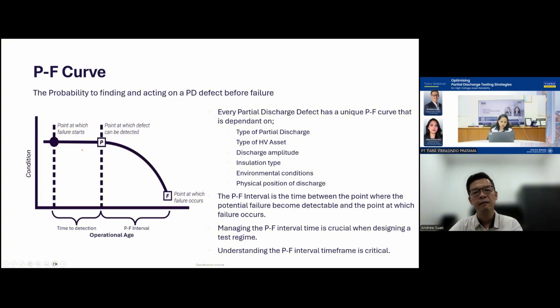Okay, and then number 3, the discharge amplitude. In EA Technology, we have a guideline, the same as when you are using an instrument to pick it up. Our guideline is that 0 or 1 to 19 is still within the safe zone, although there is PD. From 20 to 29 is the amber zone. Amber means maybe there is some form of defect already, getting from bad to worse. You may want to take action ASAP.